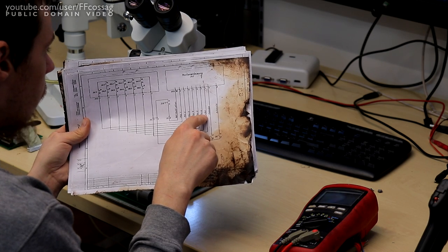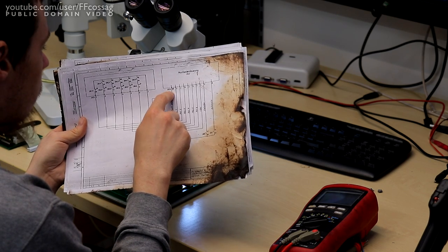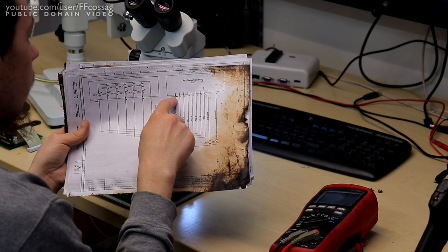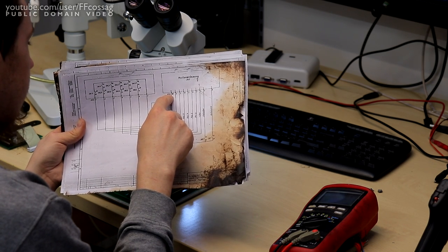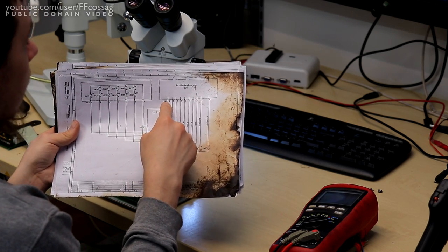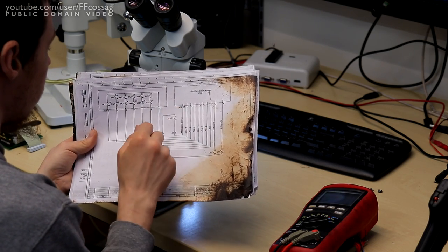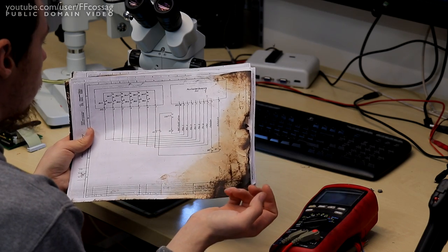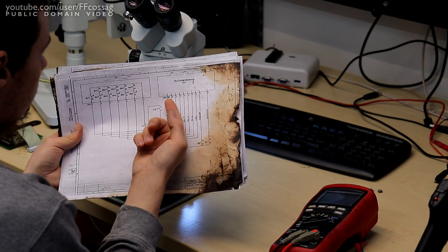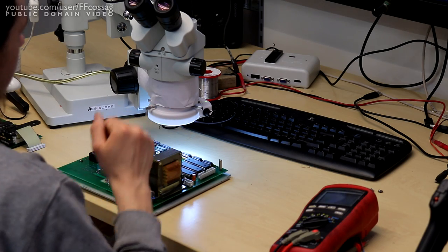So essentially, we're looking at an input on pin 10 here, and I happen to know which connector this is thankfully. That's supposed to be low when the switch is not active, and high when it is active. Just zero volts, 24 volts logic, very simple, brutish stuff. So we know what to look for. It's voltage dependent, probably going through resistors straight into the optocoupler. So now the next step is going to be to see where this connector is on the board, and see which piece on here it actually goes to.